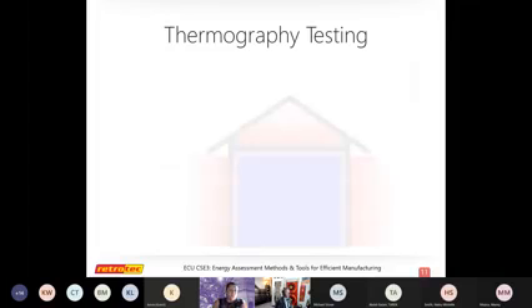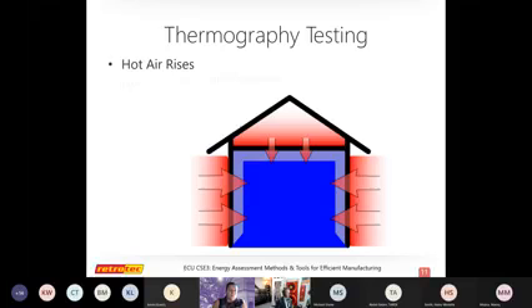And as we're running our blower door system that I showed you at the beginning, what we're doing essentially during that test is exaggerating all of the leaky points in that building to measure it. As we're doing so, if we're able to walk around that building with a thermal camera, we can really see where those problem areas are, especially if we have a good temperature difference between inside and outside. So during the winter months and the summer months are the best time to do that. You can test anytime, but to really get good, nice photos of where the problems might be with a thermal camera, peak seasons for winter and summer are best.